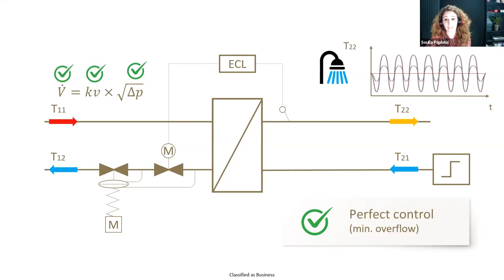But there are still cases, however, where this is not possible. For instance, where you're looking at oversized valves or uncommissioned controllers. However, in those cases, the results with the motorized control valve will still be better than having no control at all. So in recent years, we've looked at using PICV controls, which basically combine the motorized control valve and the differential pressure controller into one complete unit. Next slide, please.